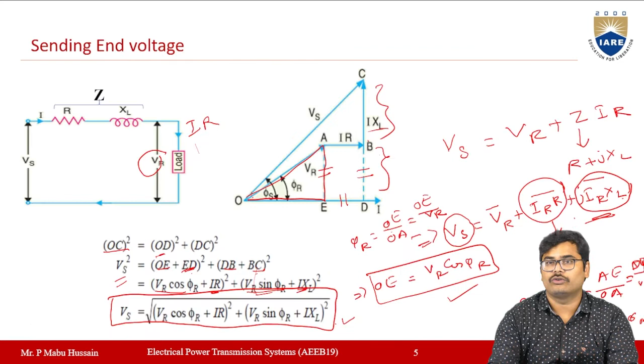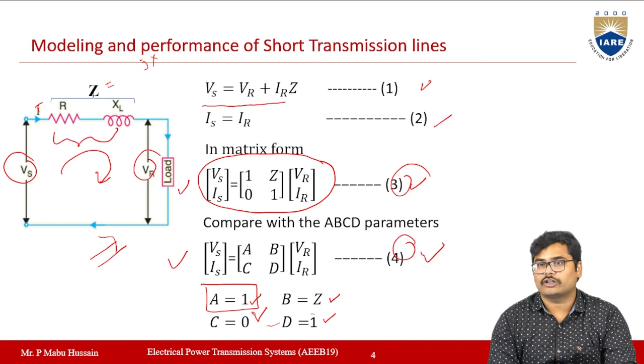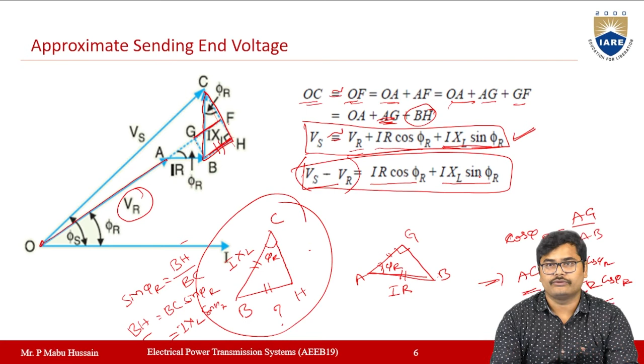For short transmission lines, the value of A we already derived will be equal to 1. So you simply substitute 1 there, and the percentage voltage regulation for a short transmission line will be Vs minus VR by VR into 100. From the previous slide, Vs minus VR is IR into cos phi r plus IXL into sin phi r. You substitute that in place of Vs minus VR, so the voltage regulation will be this value by VR into 100.